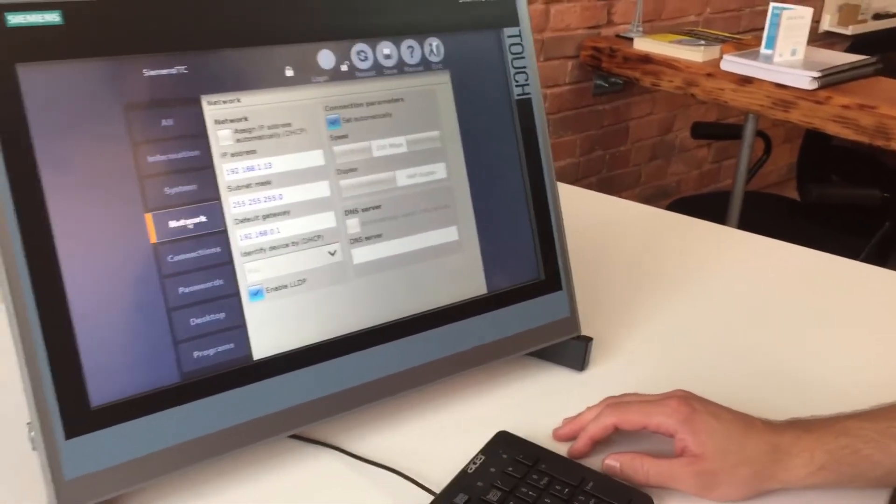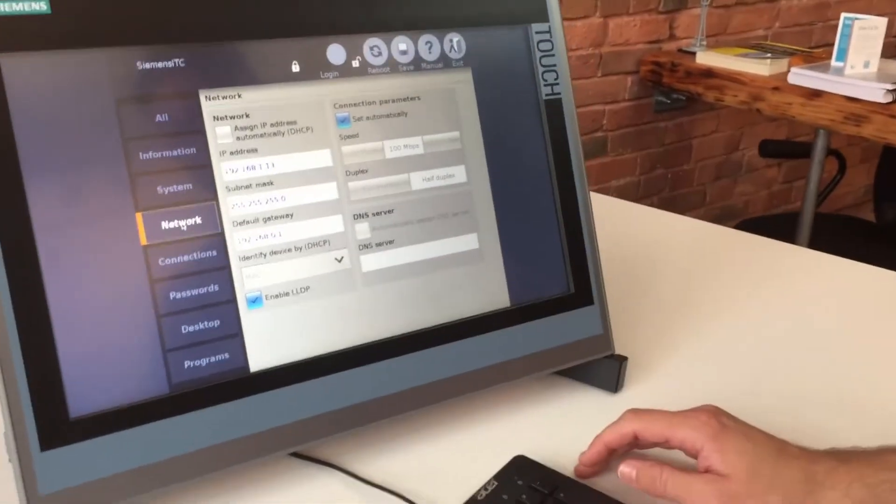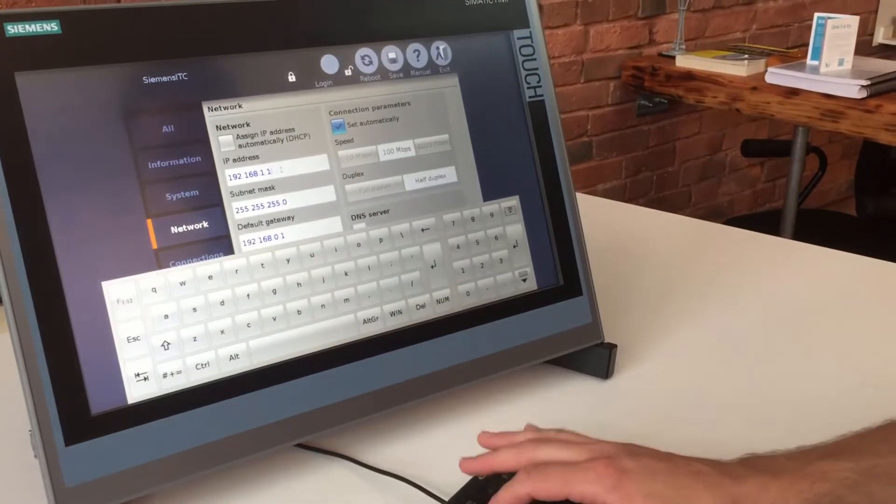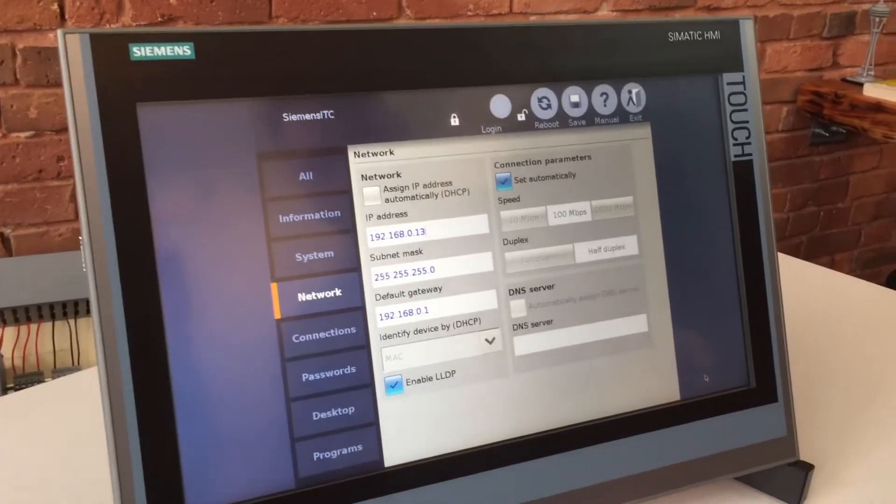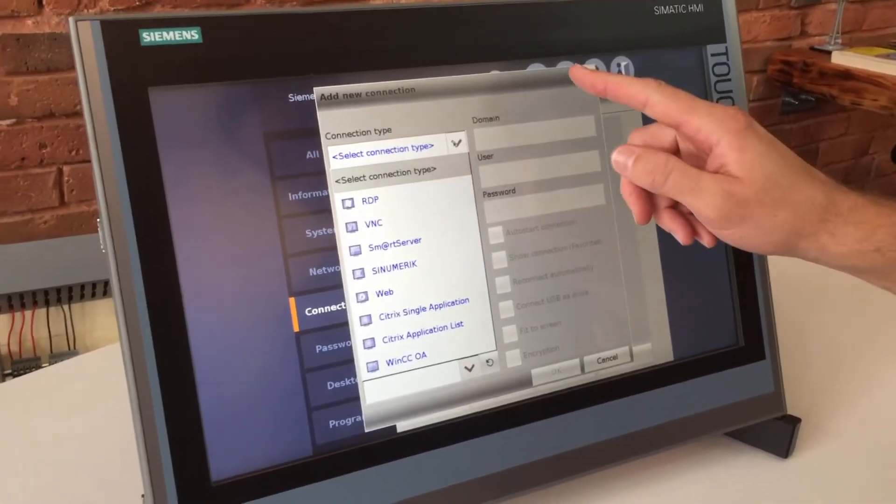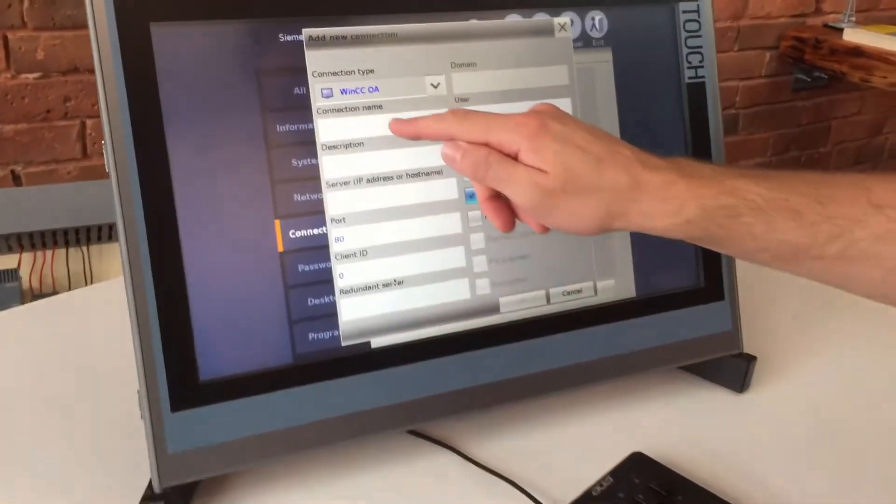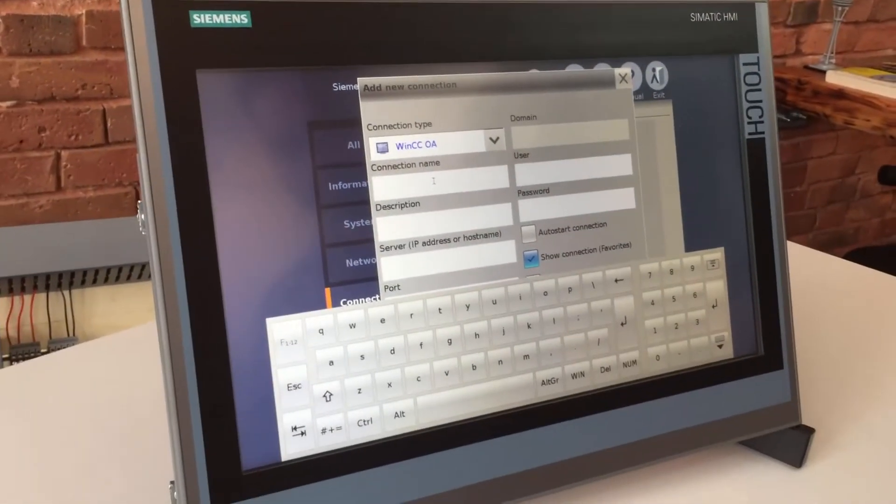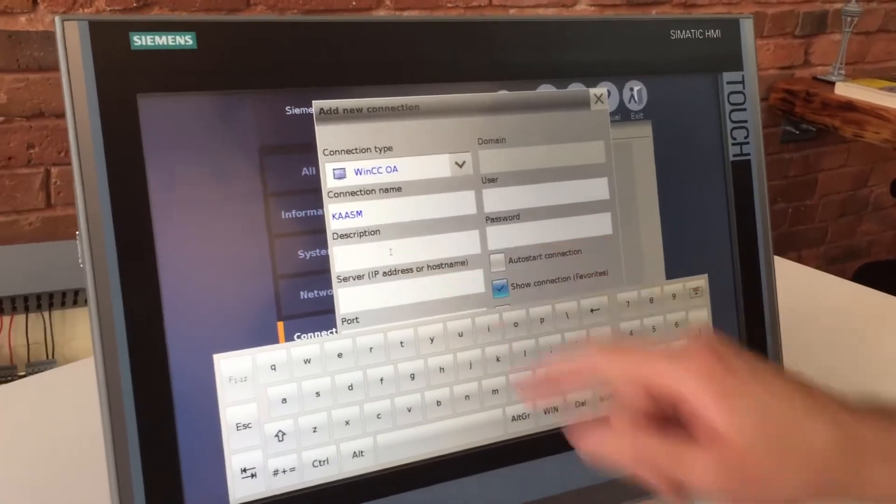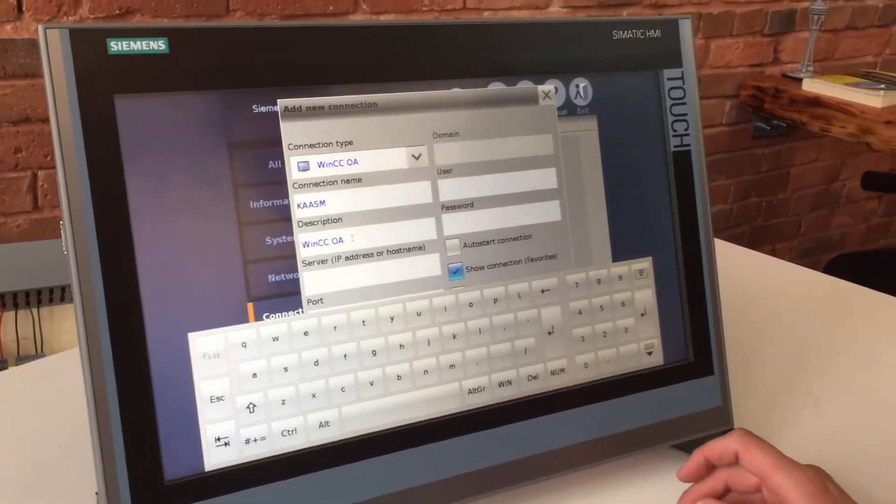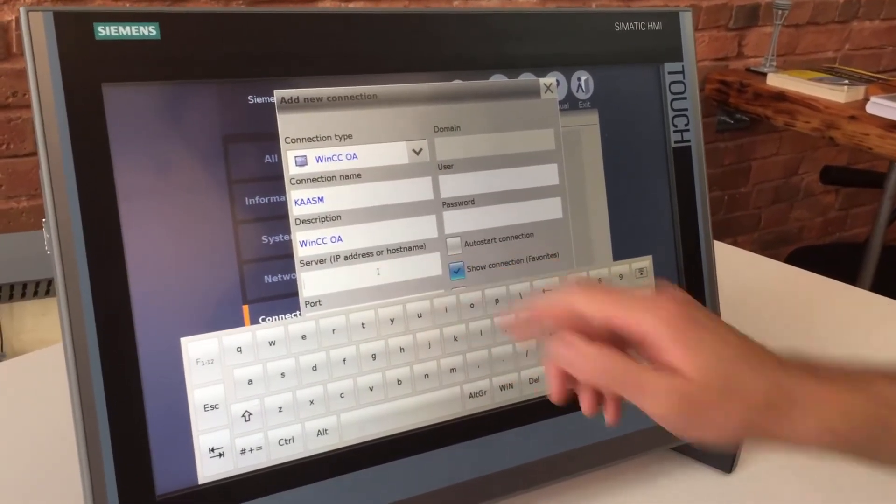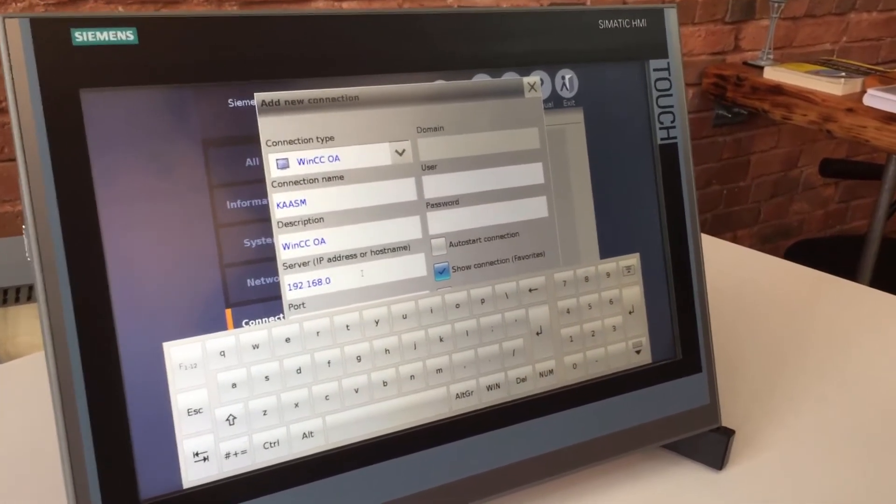So we want to give this device an IP address so it's on the same network. So let's make that 192.168.0.13. OK, and then click Connections and let's click New and hit the drop down box. And we should see something that says WinCC Open Architecture OA. There it is. All right, give the connection a name. Let's call it KAASM and description. Let's call it WinCC OA. And then let's put the server IP address in there. And that is 192.168.0.101.